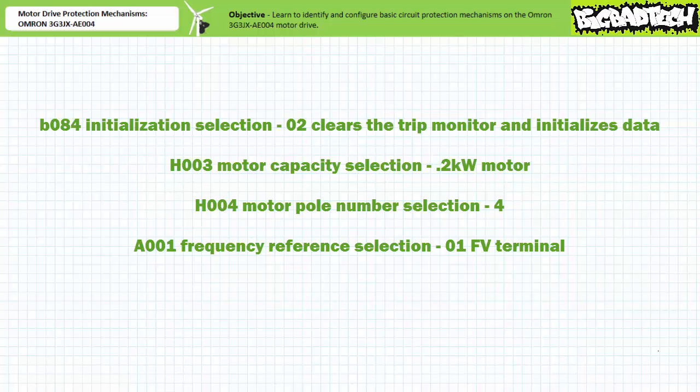Since we'll be dealing with this particular manufacturer's parameter programming process, it may be helpful to download the associated datasheet and user manual. Before making use of the OMRON 3G3JX AE004 motor drive, we'll initialize the drive to a default state and clear any errors using initialization and protection parameter B084. Then we'll program it to recognize a 200 watt motor with a nominal rotational speed of 1800 RPM using motor settings parameters H003 and H004.